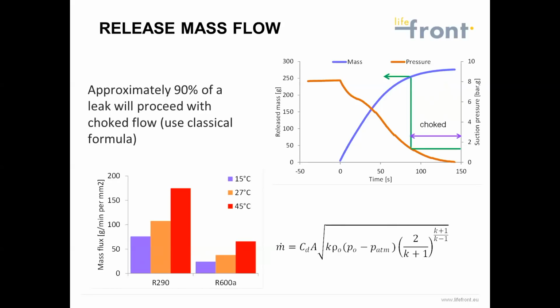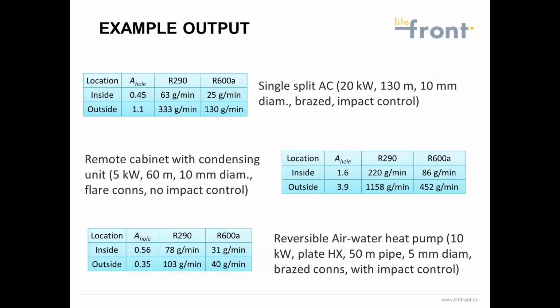So for example, if all of your high pressure parts are outside, then you don't need to consider a saturated vapor pressure of, let's say, 45 degrees C or 55 or whatever, occurring from leaks within the occupied space. And similarly, if systems operate in reversible cycles, then you may want to consider that. So this approach is a basic thermodynamic approach that we use on a day-to-day basis, but it helps us provide more confidence in determining charge limits.